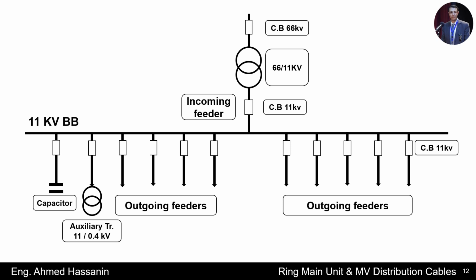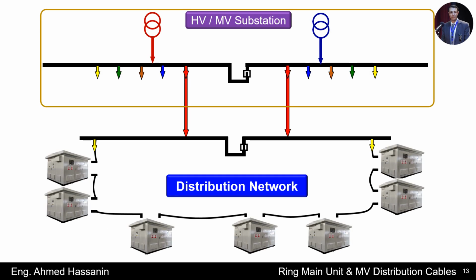Let's ask an important question. Is the medium voltage incoming cell or incoming feeder separated from the other outgoing feeders as shown in the single line diagram, or with a different arrangement like the previous medium voltage switchgear photo? I will talk about this point in detail. I will talk about the main components of the medium voltage distribution network. We see many kiosk transformers in the distribution system, and we will know how they are connected to each other. In addition, I will talk about how the medium voltage distribution networks are connected to the high voltage medium voltage substation.